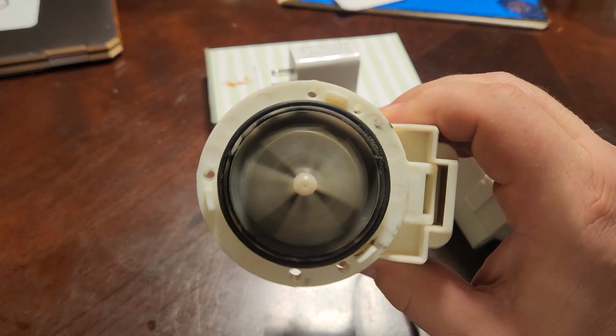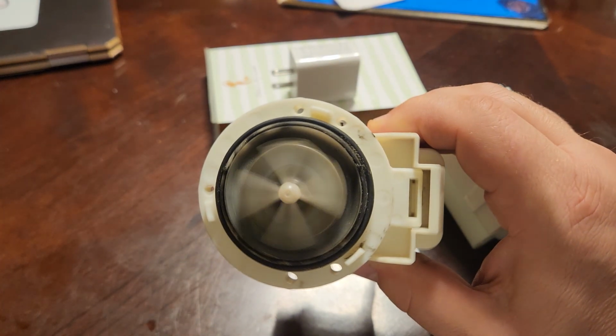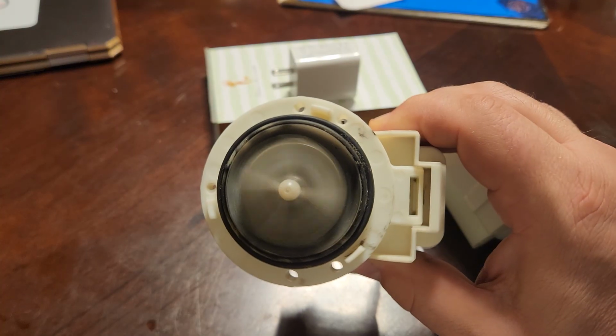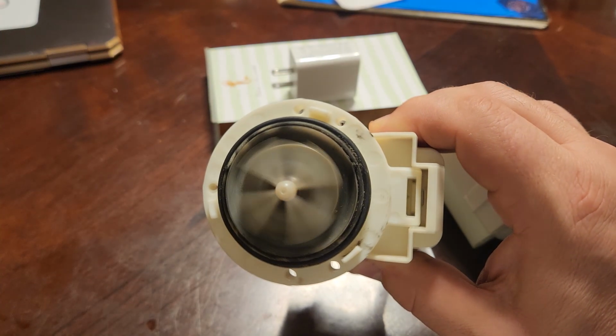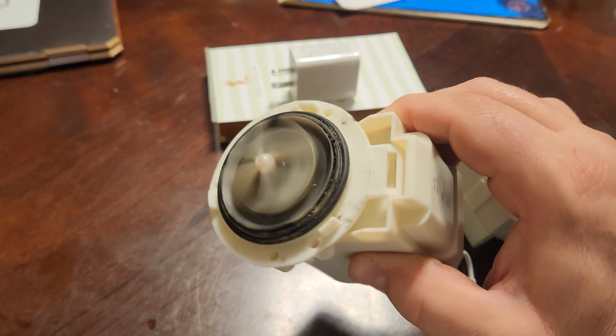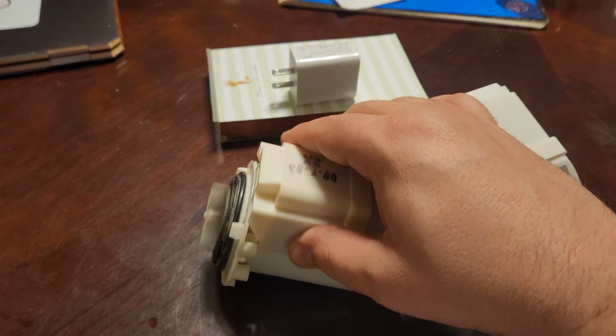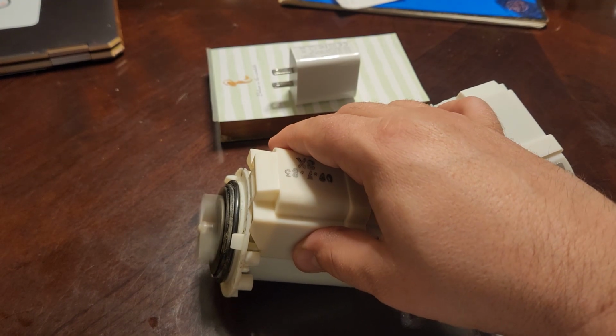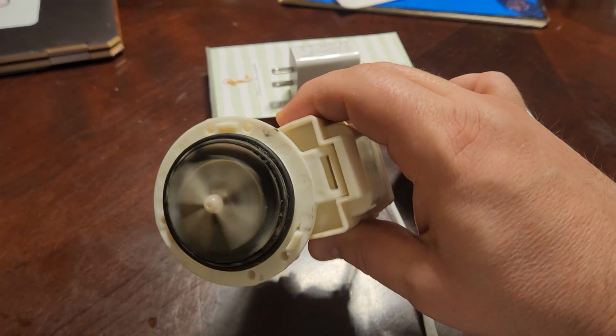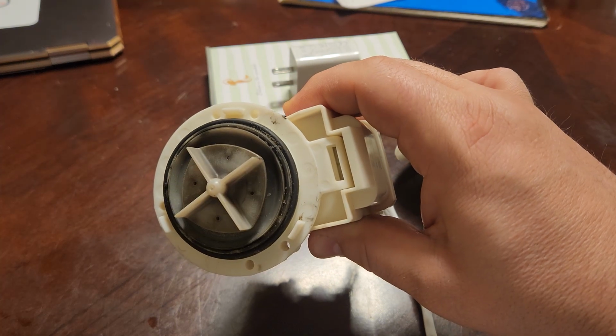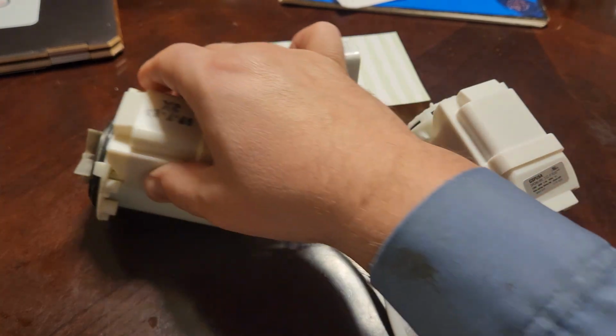Running test results. The motor does run, but look closely. You can see vibration. The impeller rotation is uneven. It speeds up, then slows down. That's not normal, and I believe once this pump is under real water load, it performs even worse.